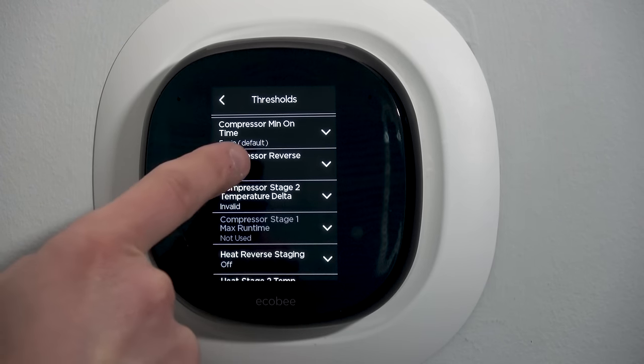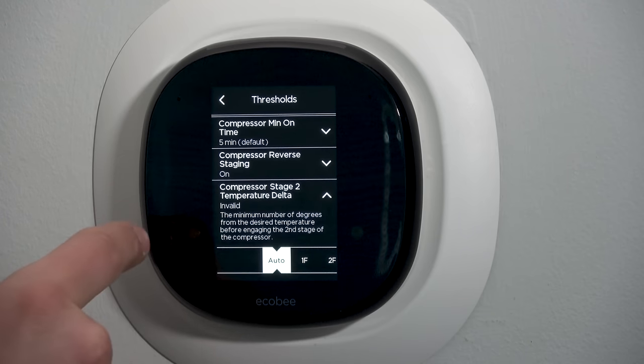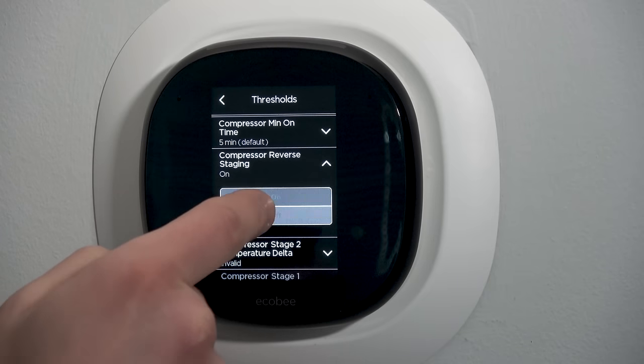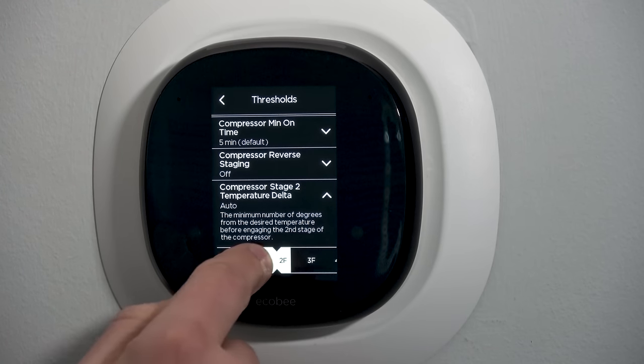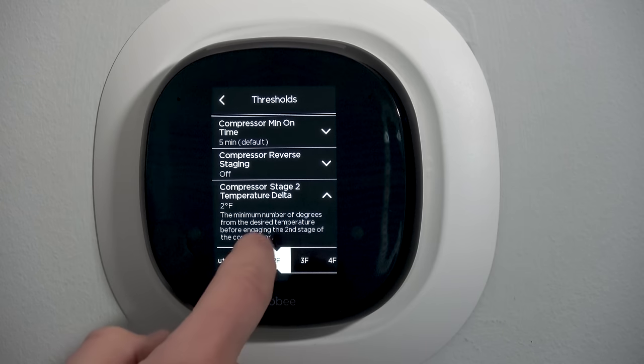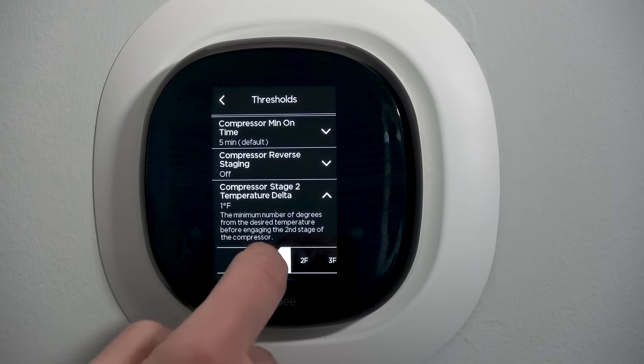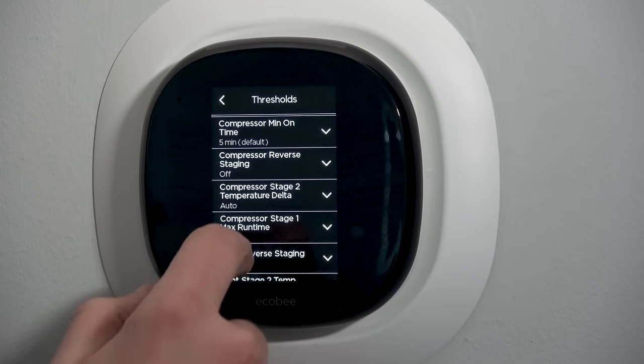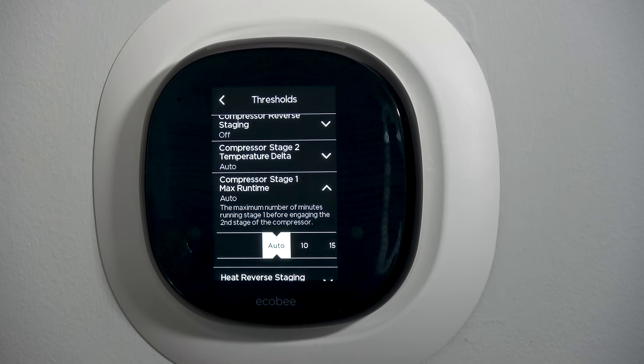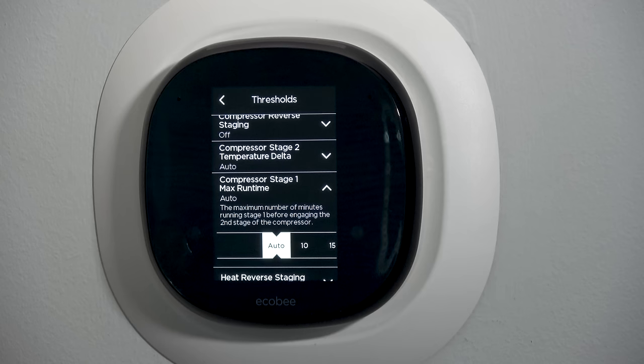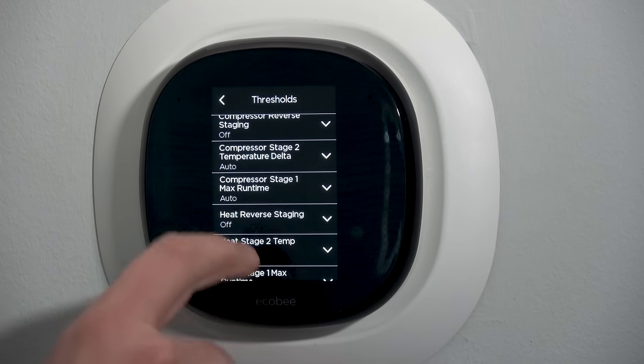With reverse staging off, I have access to the stage two temperature delta — when the second stage actually comes on, whether that's one, two, or three degrees above set point. You can't make it faster than one degree because it would turn on before first stage, which wouldn't make sense. You can also leave it in auto calculation mode. Compressor stage one maximum run time: the maximum minutes stage one runs by itself before forcing into stage two. I usually leave that on auto — you can put a timer on there but it requires you to know a lot about the house.